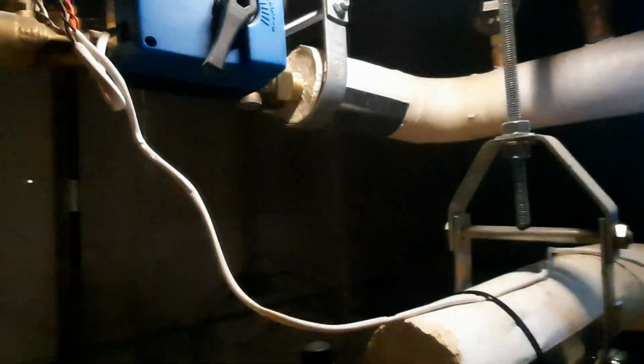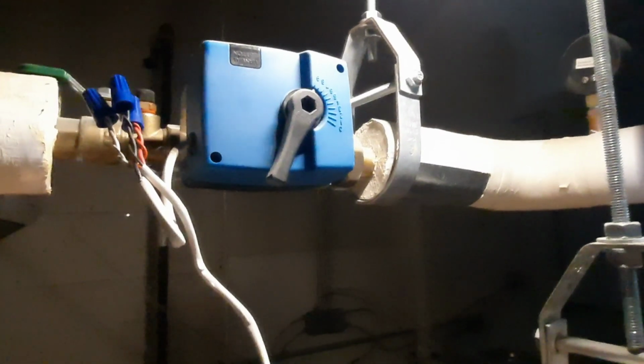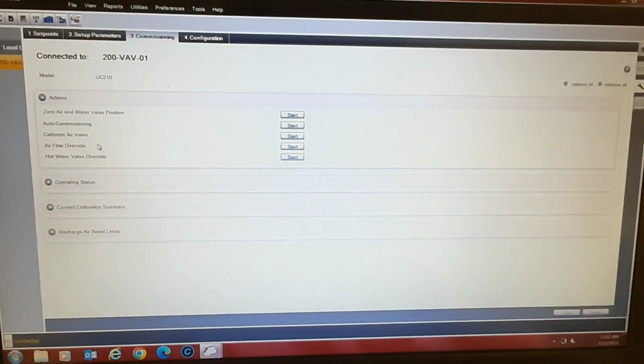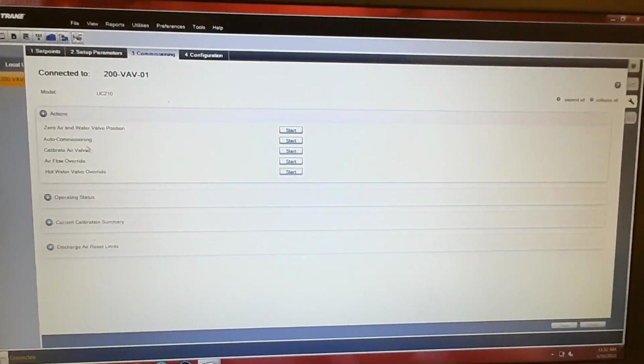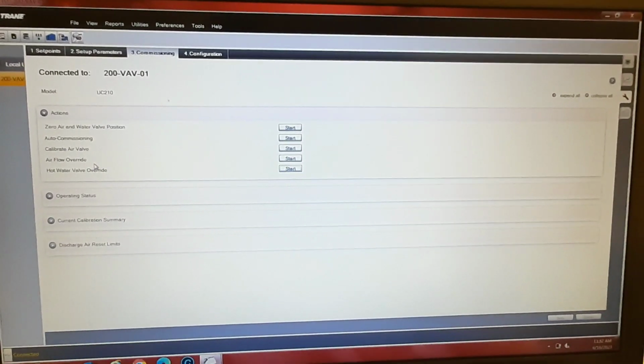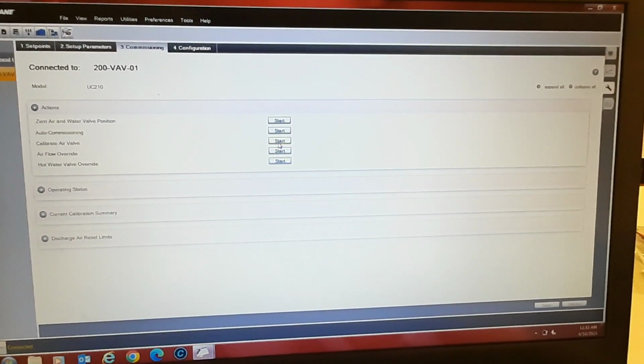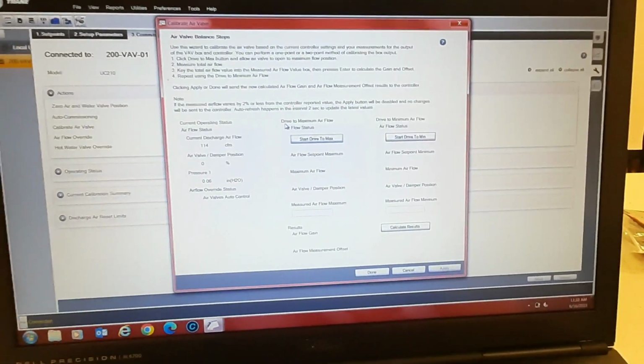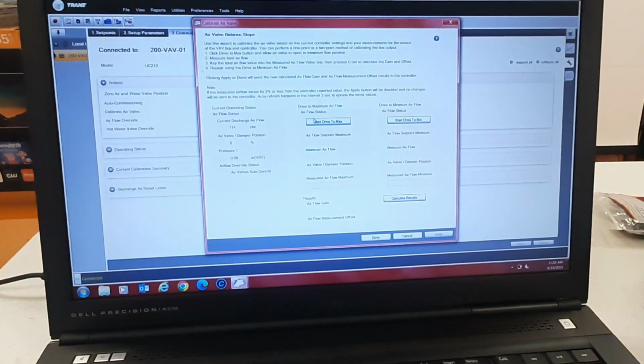We can also see that orange LED, that's our binary output for our valve. So we're at 100%. We're gonna go ahead and put that back to normal, let it close, and then do the same thing with our air valve. So let's go do calibrate air valve. Do the same thing here.